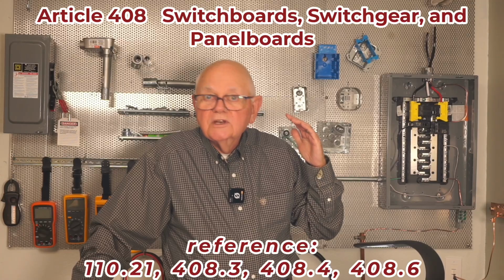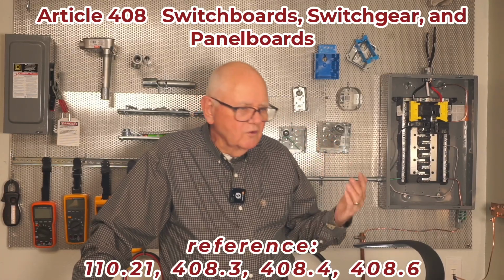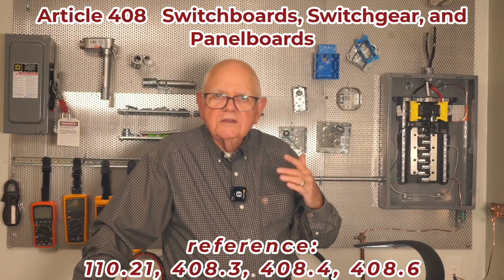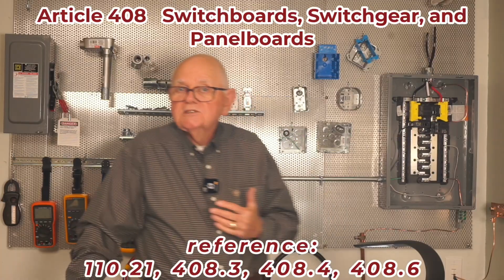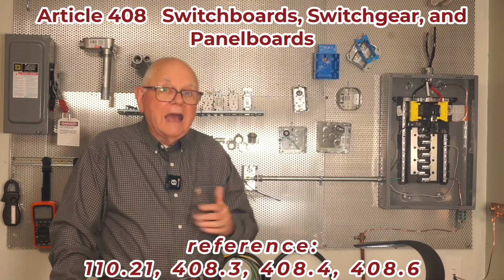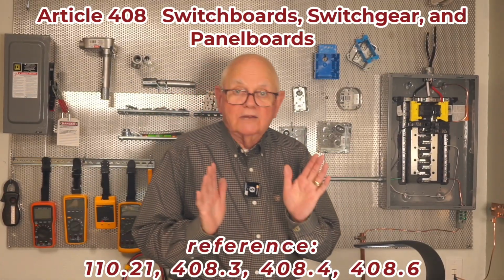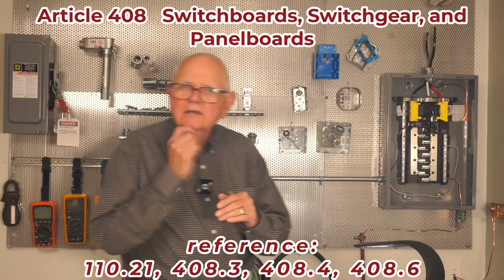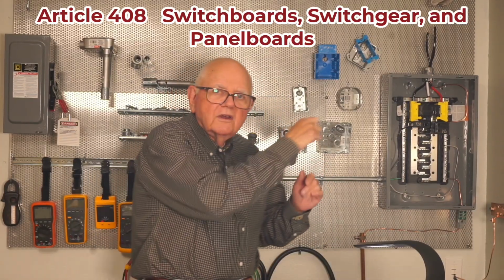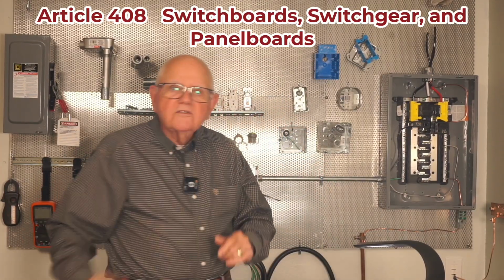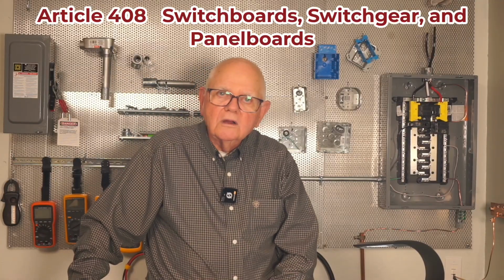Those markings are going to have to be durable. They're going to have to be suitable for the environment. They're going to have to be legible. One specific location says they can't even be handwritten. Even if I've got beautiful handwriting, which I don't, I can't take out my black Sharpie and nice and neat print on there one of the requirements that I have in 408.4.